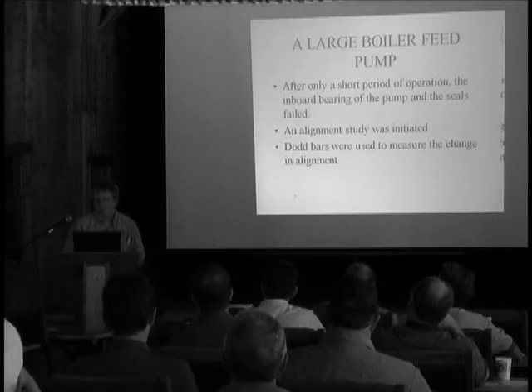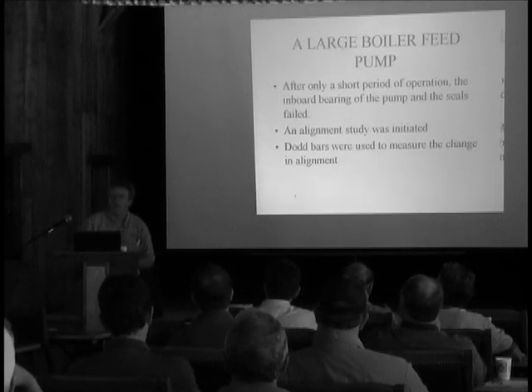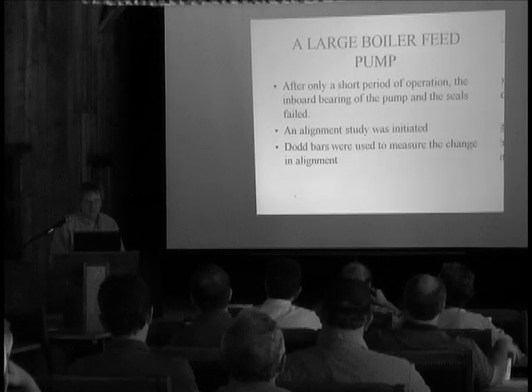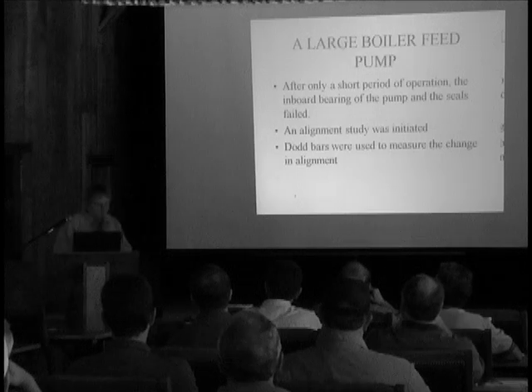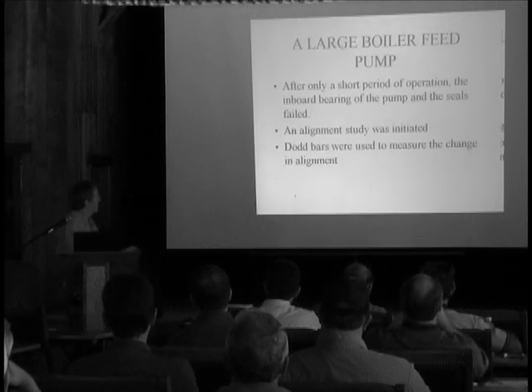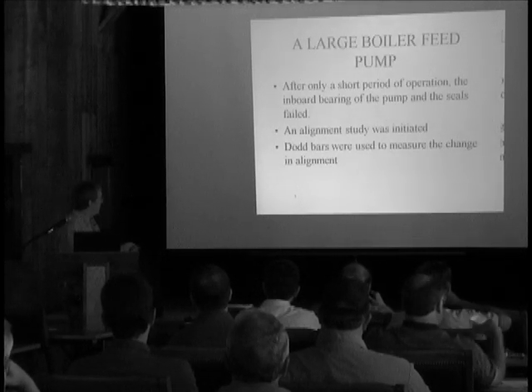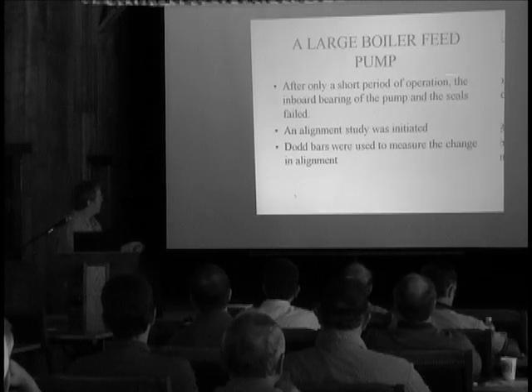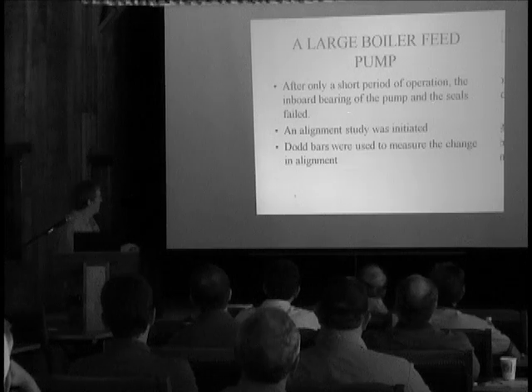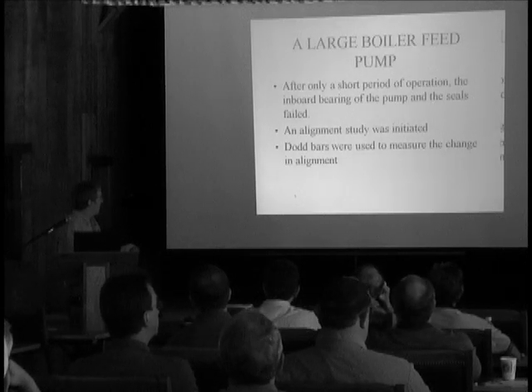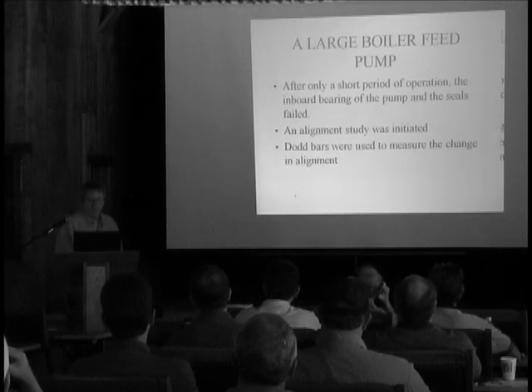And it turned out there were several of these plants, and they all had the same problem. But anyway, I thought that problem was the problem that wouldn't go away. Here's a large boiler feed pump, and after only a short period of operation, the inboard bearing of the pump and the seals failed. An alignment study was initiated.